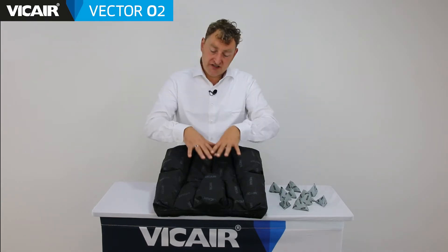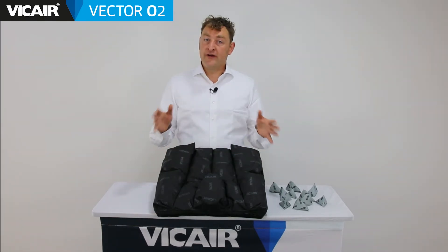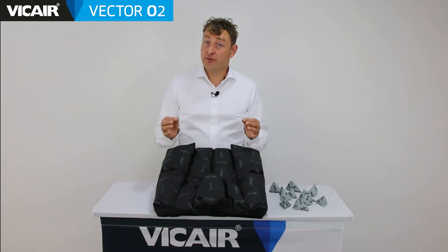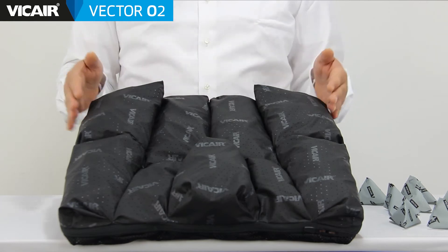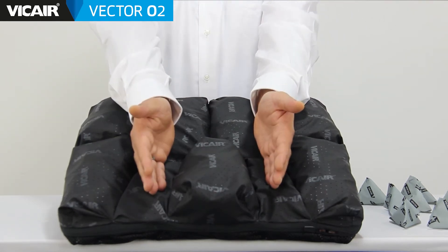The Vicair Vector O2 is a pre-contoured cushion which consists of nine compartments. Pre-contoured means that the cushion already has an outline of the shape of the body before it's loaded. Each compartment is designed to influence a specific area of the pelvis, striking a unique balance between preserving skin by redistributing pressure at the ischial and coccyx area, stabilizing the pelvis and positioning the femurs.